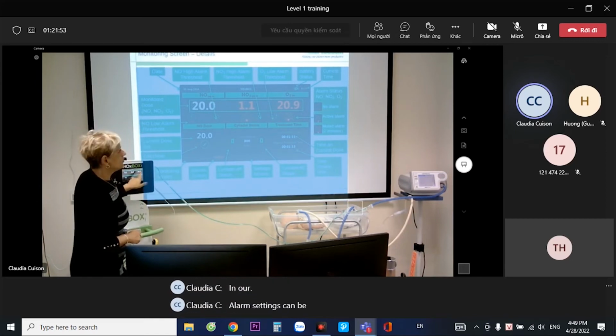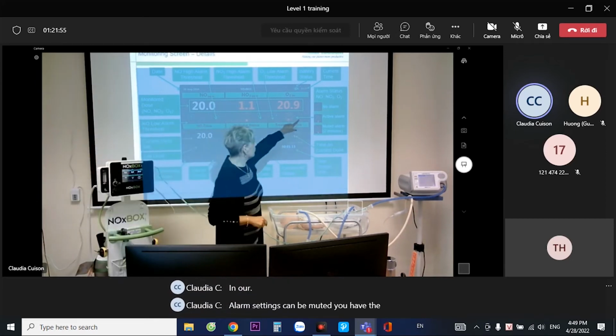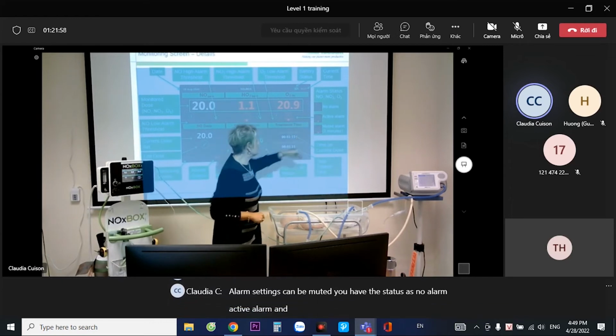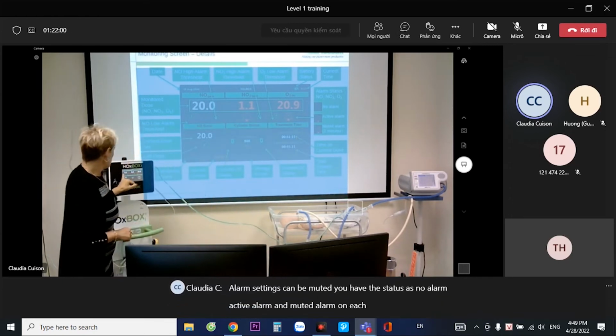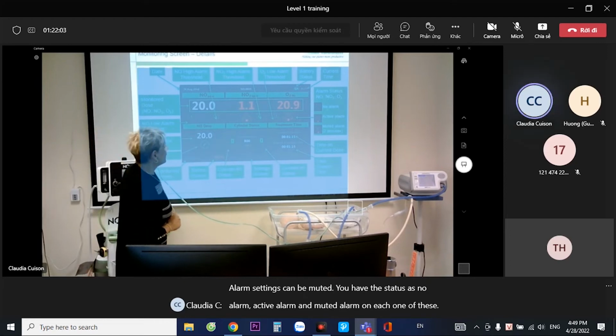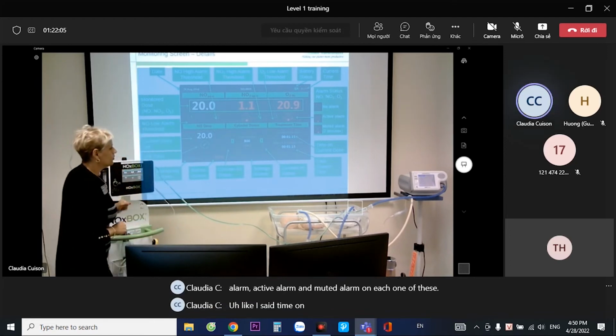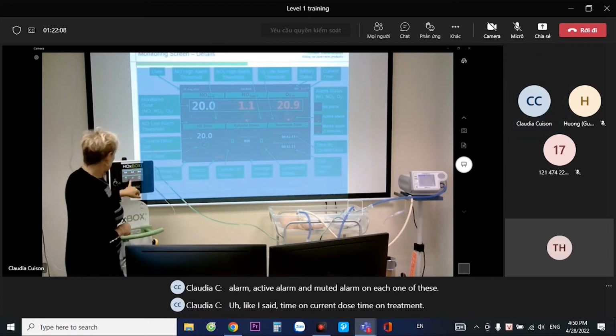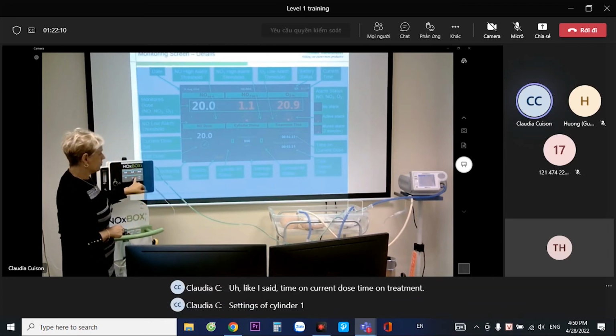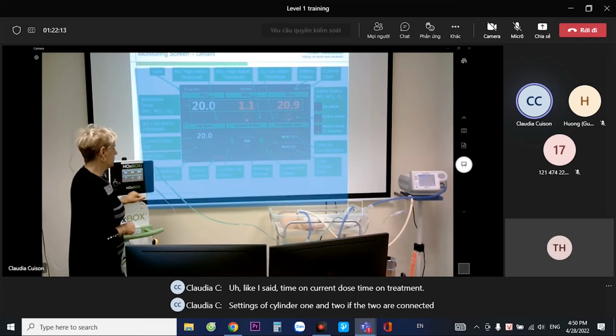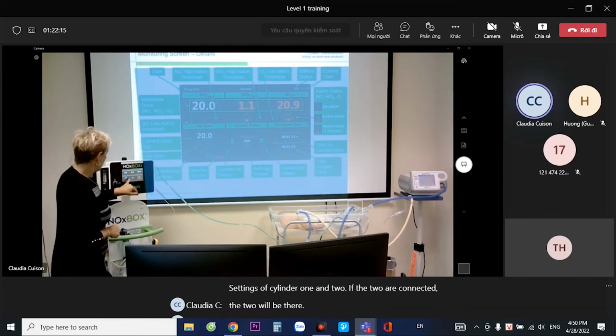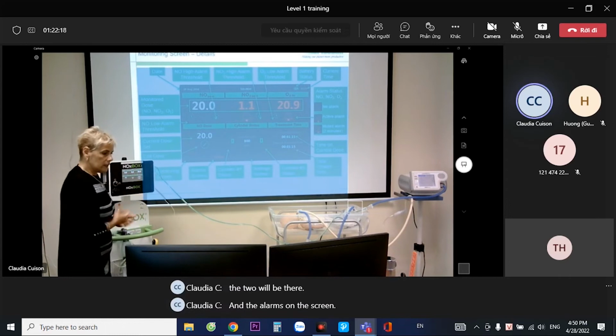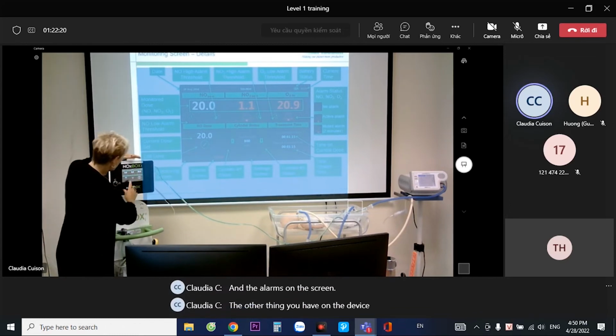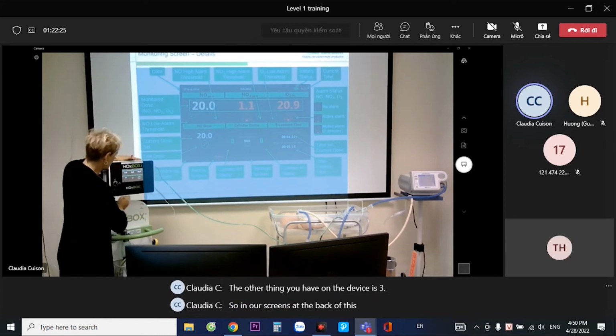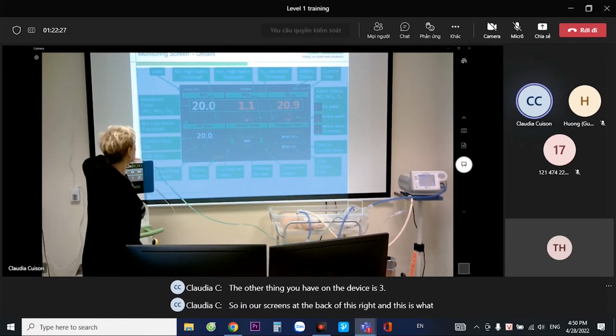At the bottom level, you have the NO dose. To edit, you just press the pencil to change the nitric oxide dose, and alarms will be reset to align with the new dose. Like I said, this is automatic. Cylinder status, you have the cylinder status empty or with a concentration reminder as well. And here is an important part, which is the treatment time, this part here, okay, this treatment time.